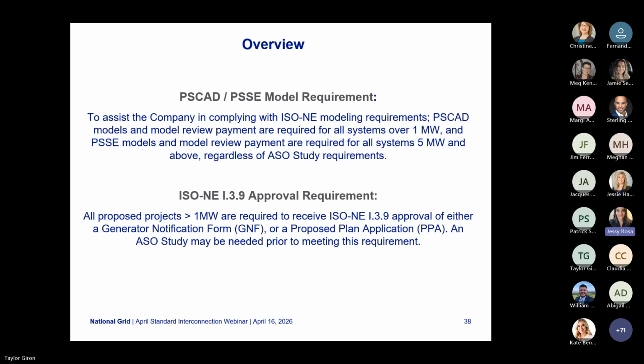So either of these models and payments will be required based on the size of the system, either the PSCAD or PSSE model. For all systems over 1 megawatt, a PSCAD model and model review payment is required. For all systems 5 megawatts and above, you will need a PSSE model and model review payment, regardless of ASO study requirements. For all proposed projects greater than 1 megawatt that are required to receive ISO New England I.3.9 approval of either a GNF, which is a generator notification form, or a PPA, which is a proposed plan application, an ASO study may be needed before this requirement.